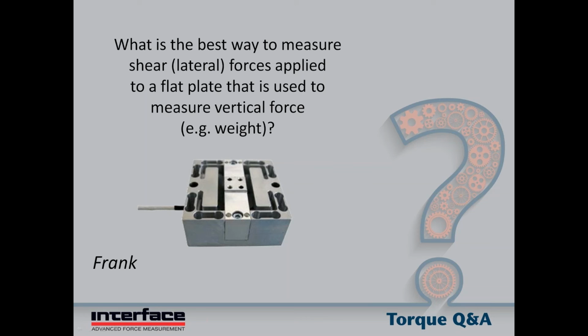Whether you use one load cell or several in this type of application depends a lot on the geometry of the test. So it's not necessarily better to do it one way or the other until you understand what the load points are. And with these types of sensors, we usually want to talk about the geometry, as in if it's a shear force but it's applied 2 feet off the surface, there's a lot more going on than if that same shear force is applied right at the surface. So we need to understand not only the magnitudes and the orientations of the loads, but the geometry of where they're applied. Hopefully that answered that question.